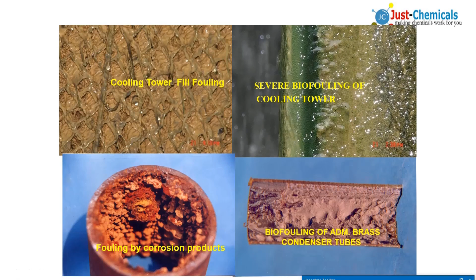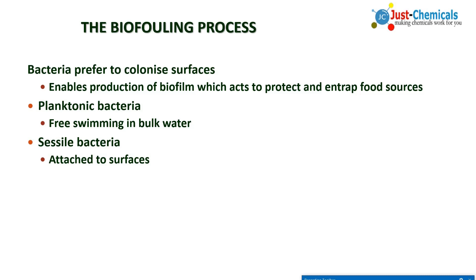There are two types of bacteria actually. One is free swimming in bulk water, which we measure through the dip slide method. Normally in power plants, we use dip slides to count the bacteria, TBC and SRB. So when they are free swimming or planktonic, we can measure them. But if they are sessile, attached to some surface, we will not be able to measure them. And that is why biodispersant is important, because biodispersant can make the sessile bacteria float in the water.